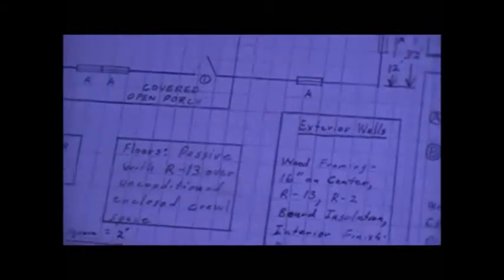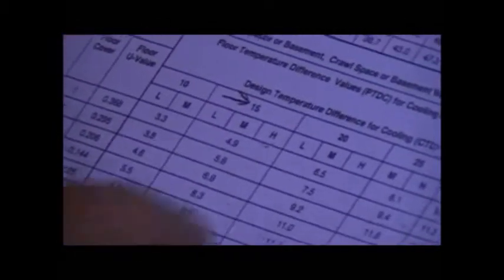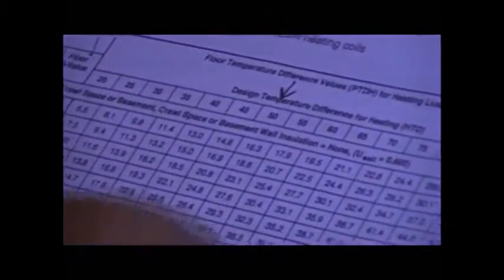Okay, so we need to look at this information and we have both heating and cooling criteria here in the J manual. Our first part is for the heating, and we're going to use in both cases a 19A-13P, for the upper and the lower one. And we're going to come up with a 50 degree temperature differential. The PTDH is going to be 36.6, I believe that's what that reads, with a U value of 0.065. That's a lot of information to remember, so let me get a little bit at a time here. I come up first with a 19A-13P, so let me do that.